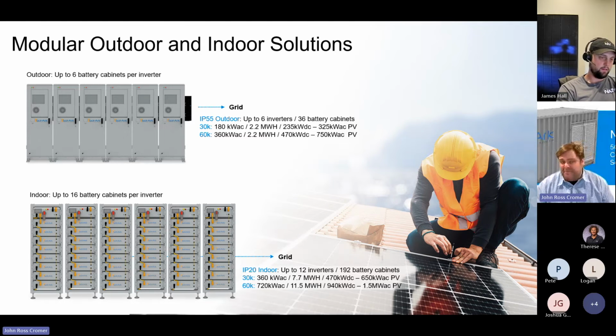For backup applications, personally I would start with 2 inverters and 2 battery cabinets as a minimum project size, just for some redundancy. If it's a 200 amp service or a 400 amp service, that's great, you can have the full grid pass through. And if one inverter's on the blink, you have the other inverter there providing some power and capability into the building.